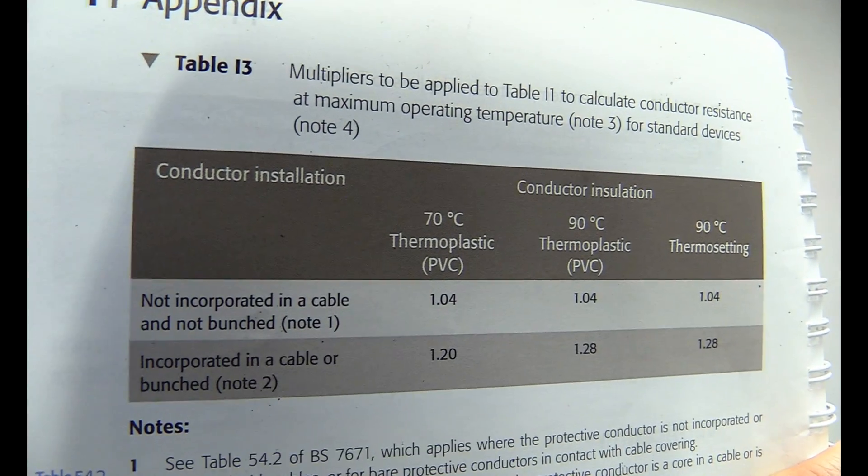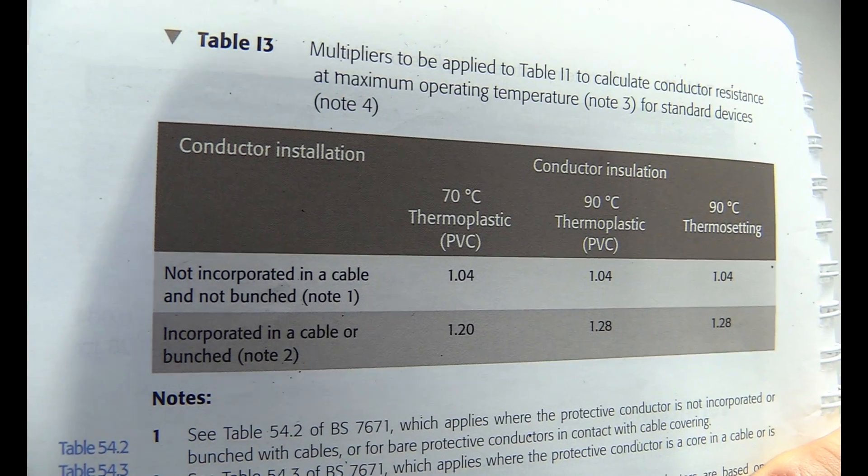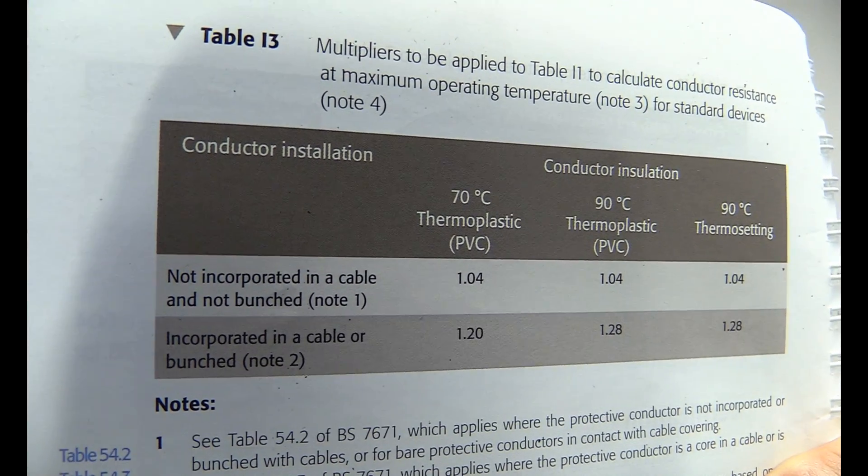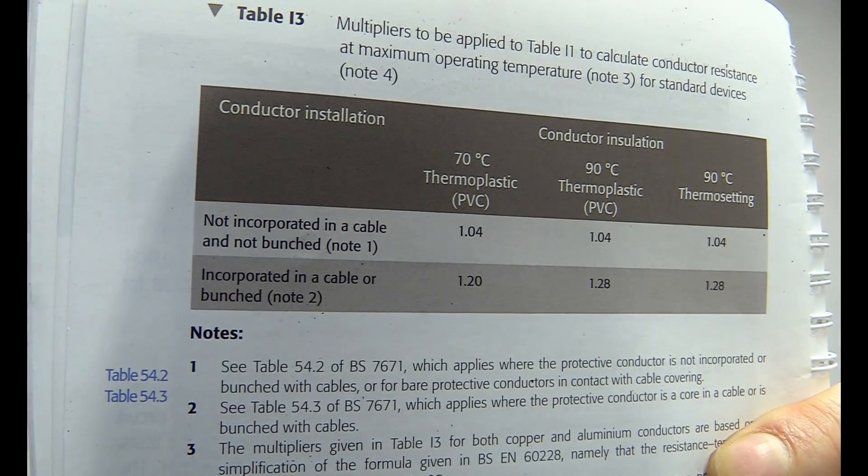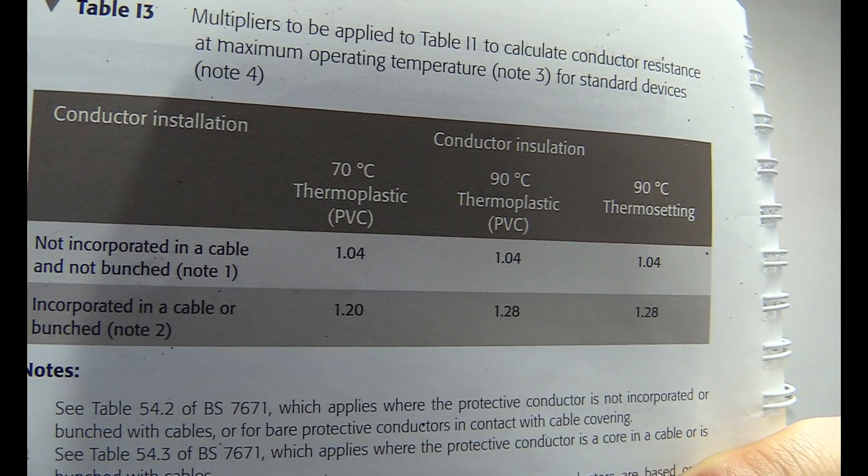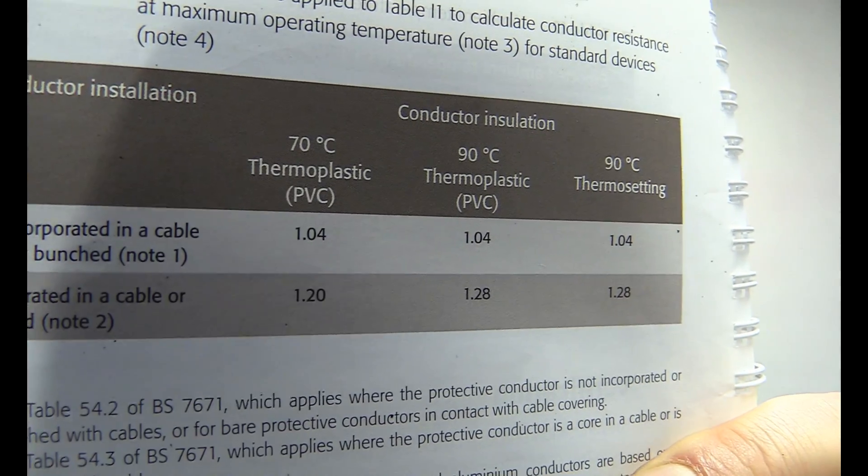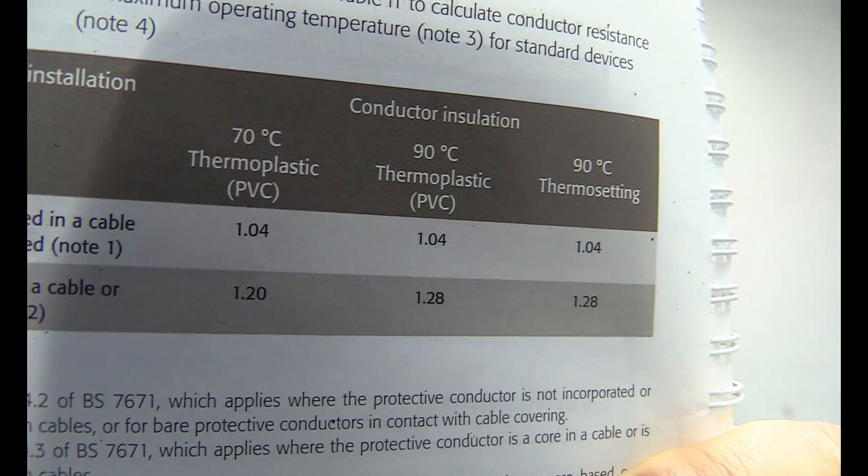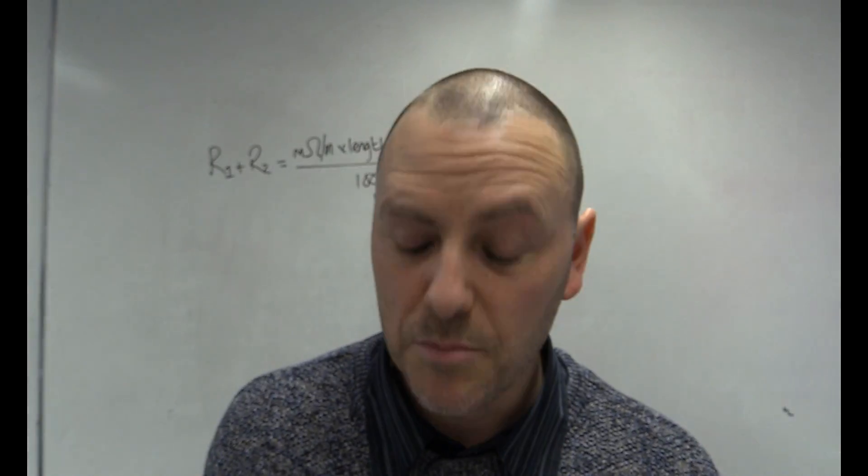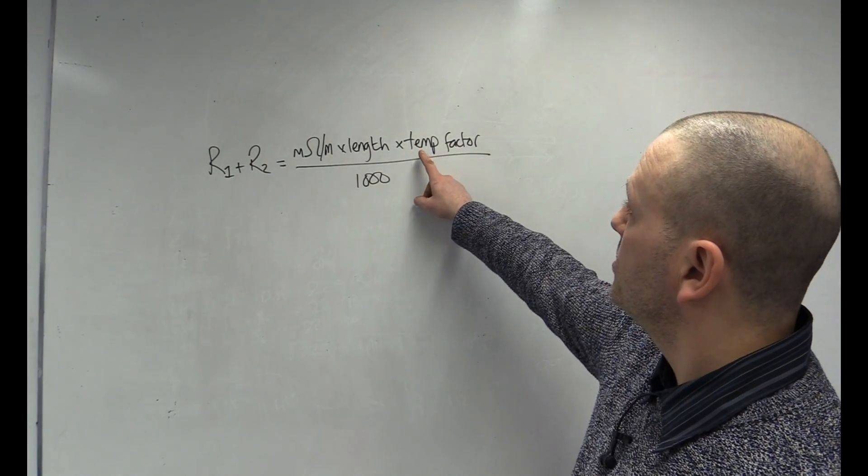You can see, for our 70 degree thermoplastic cable incorporated in the cable, or bunched, so twin and earth, or flex, or whatever, we've got a factor of 1.2, and for a 90 degree cable, same conditions, we've got 1.28, and thermosetting insulation is also 1.28, because the important thing is the temperature.